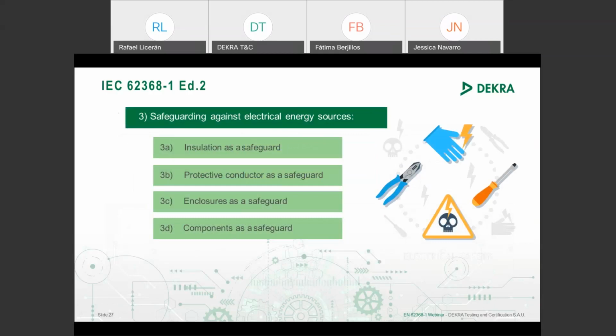Regarding the safeguards, the standard includes 4 ways to protect the user, the different operators: the ordinary person, the instructed person, and the skilled person, from a hazard. Then the designer of the product can use different types of safeguard. Insulation as a safeguard, a material such as a plastic enclosure. The designer can use a protective conductor as a safeguard; the protective earth of the socket outlet of your building installation is a safeguard.